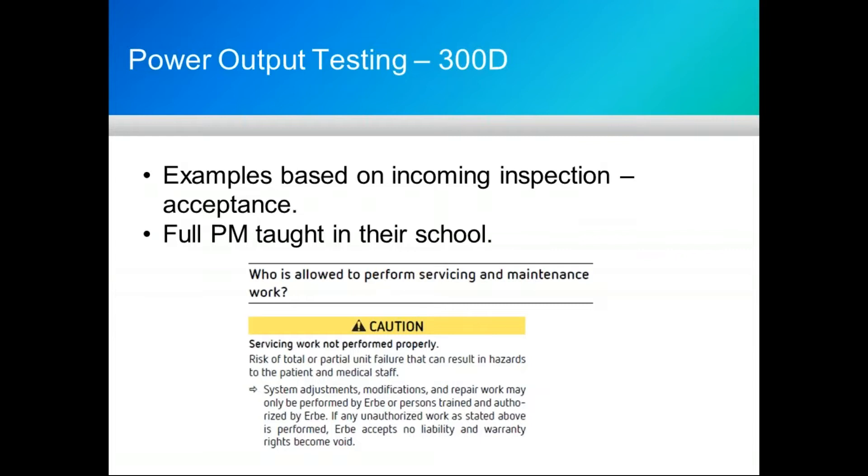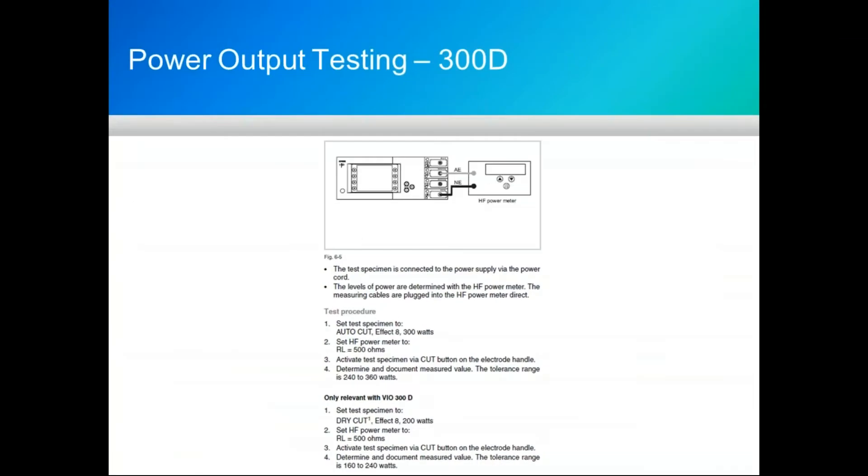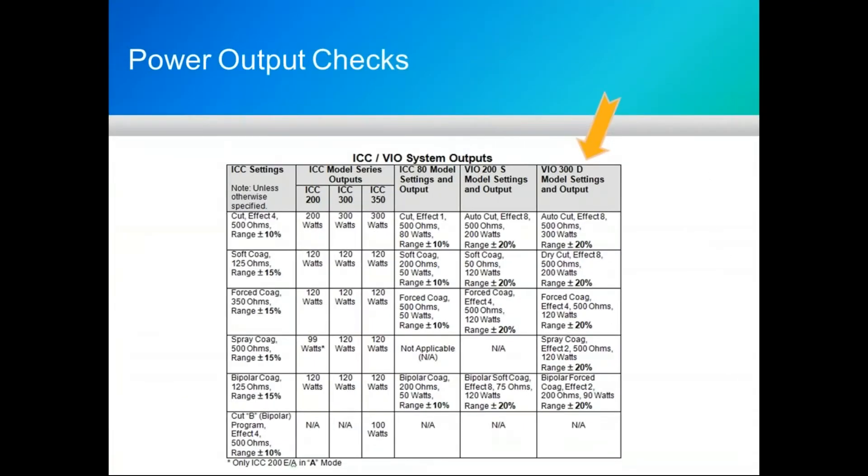Here's ValleyLab: depending on the type of test, whether coag, cut, or bipolar, they use various resistance values: 500 for coag, 300 for cut, 100 for bipolar. Megadyne units use 300 ohms for cut and 500 for blend coag. The APEX for Medtronic uses 100 ohms for several tests, 500 ohms, and then 1000 for some tests. Their tolerances are all based on power output as the ERBE 300D is. The examples we're going to show in videos are based upon the specification sheet they provide for incoming inspection and acceptance of the generator going into the facility. The full PM is taught in their training school, and we'll give some examples of that as far as test specifications. We're focused here on several power output tests, the NESSIE test circuit, and also the high-frequency leakage testing.